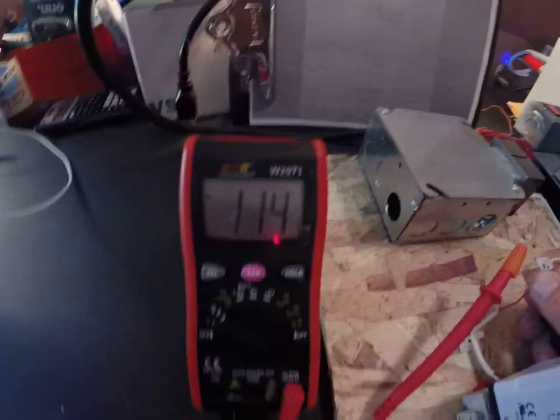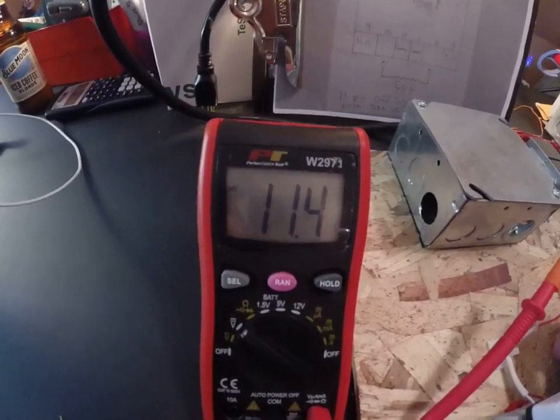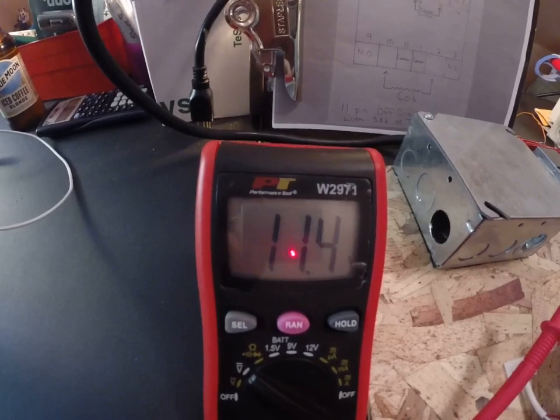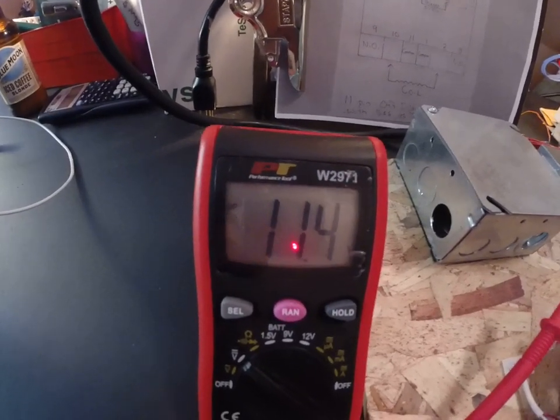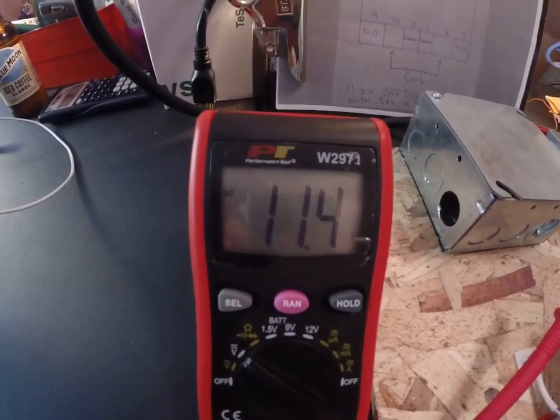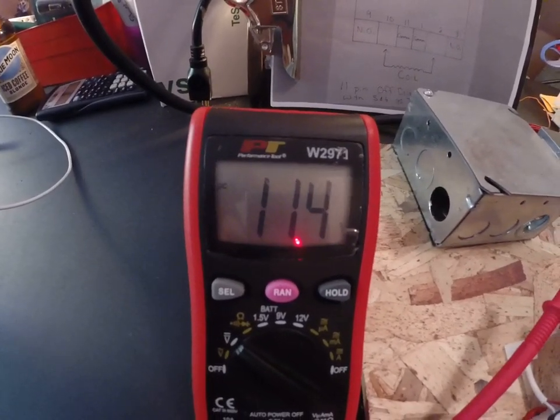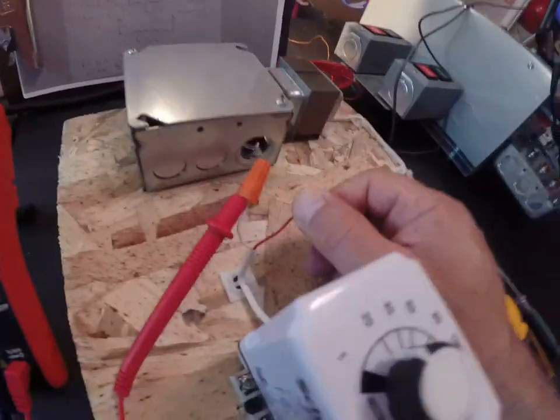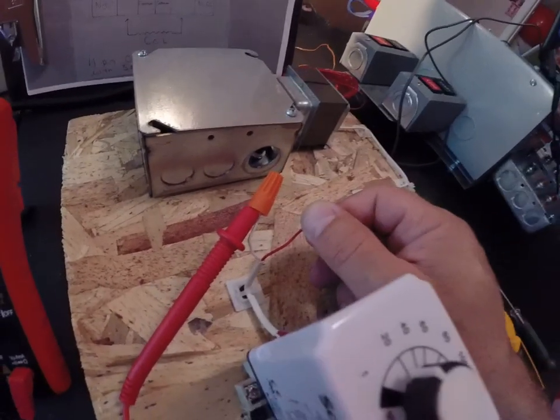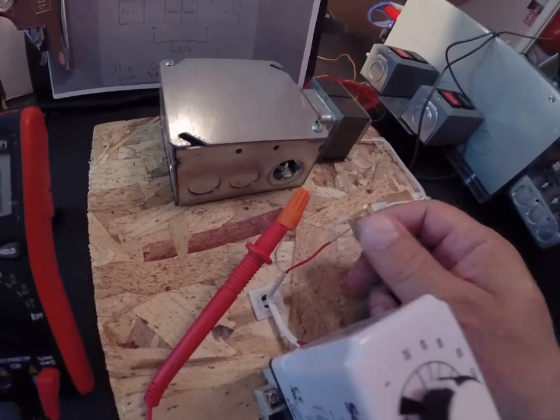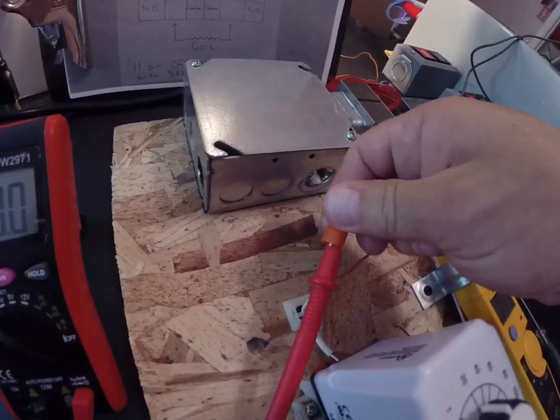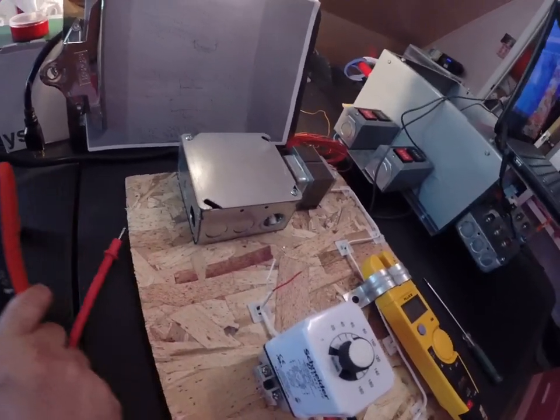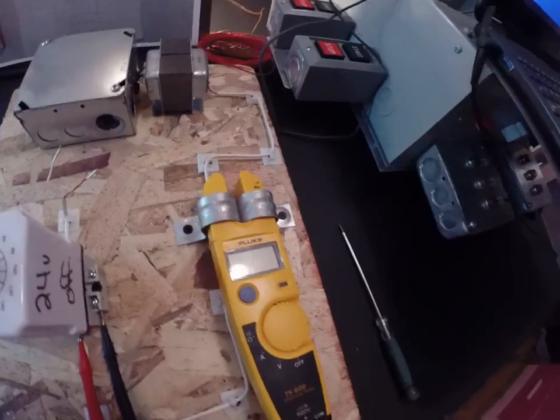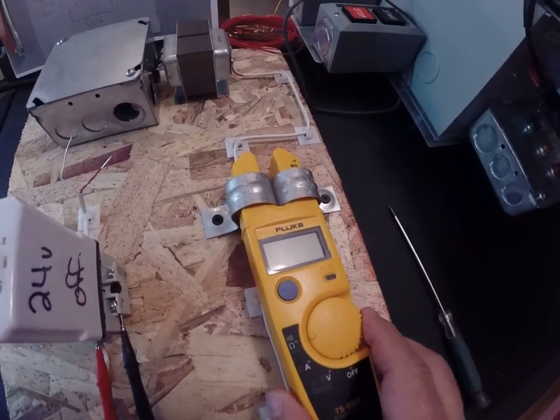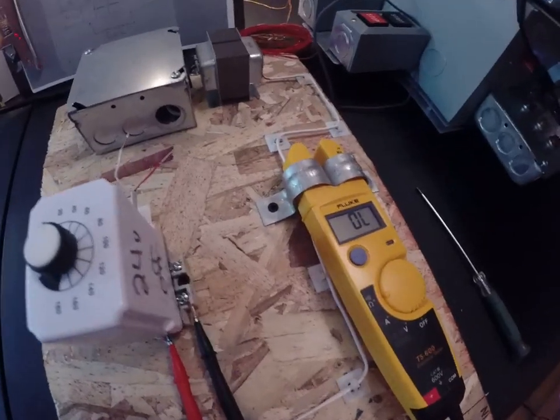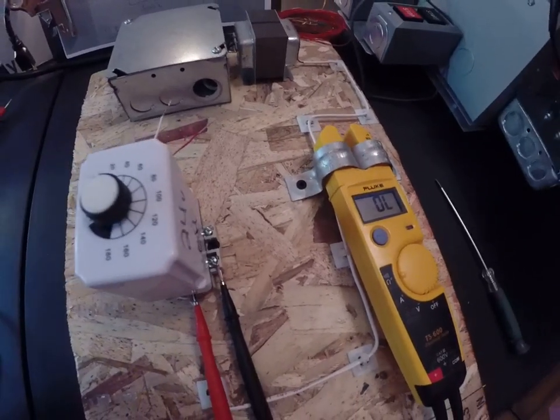Right now we've got 11.4 volts DC. That is because the coil is energized with 24 volts and the integrated circuit board inside this relay is generating this voltage at the trigger switch, and it's waiting for that short circuit to happen, or the removal of the short circuit to happen. So I'm going to disconnect this now so we can create a short circuit, and you'll see I have this other meter hooked up so I can put my meter on ohms, and I'll know by testing the trigger that my contacts actually work.